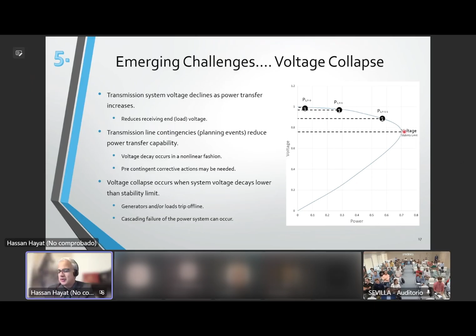So very different challenges that are being posed. We are running into interrupting capability issues. Circuit breakers that are necessary to interrupt faults on the system are not big enough, are not robust enough to break some of the faults that we are seeing on the system.